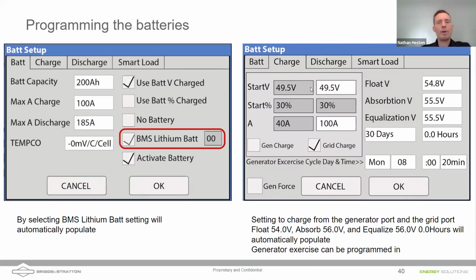If we click the charge tab at the top of the screen and go into the charge setup, you can set things like the starting voltage. Keep in mind when you're programming a Sol-Ark, you can either set the system to use voltage or battery percentage. If you have it set on battery voltage, then the percentage section is going to be grayed out for you. You won't be able to change that. So if you're going to do your settings in voltage, I would recommend that you come in here and put those settings in. If you're using the BMS feature, these settings will be auto-populated for you. These are the settings associated with charging the batteries, and these are the settings associated with charging the batteries from grid if you have that box checked.